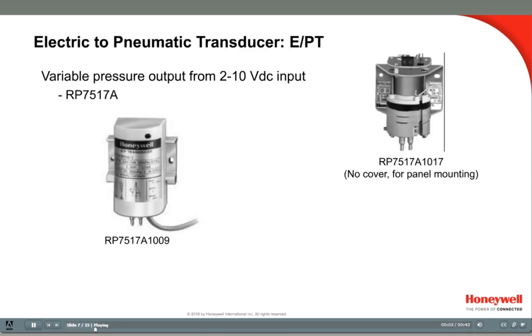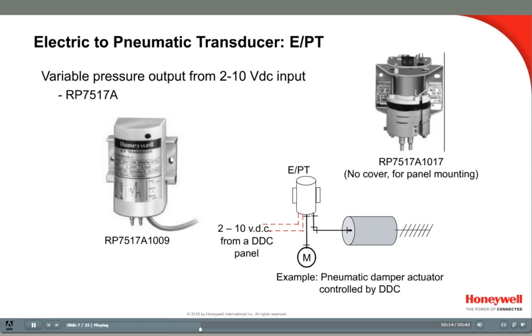Another form of an electric-to-pneumatic relay is the E-to-P transducer. This device receives a 2 to 10 proportional electric signal and outputs a matching proportional pneumatic air signal. In this example, a DDC panel is controlling the damper actuator via the pneumatic transducer. The DDC system sends a 2 to 10 volt DC control signal to the transducer, which is connected to a pneumatic damper, so it opens proportionally with the 2 to 10 volt signal. This type of application is often referred to as a hybrid system.